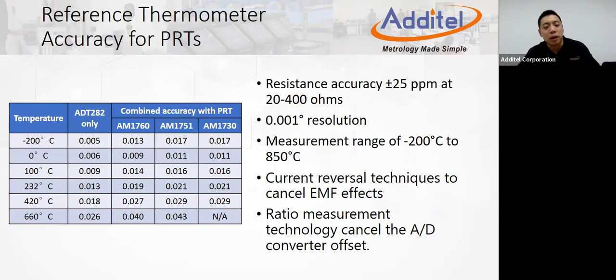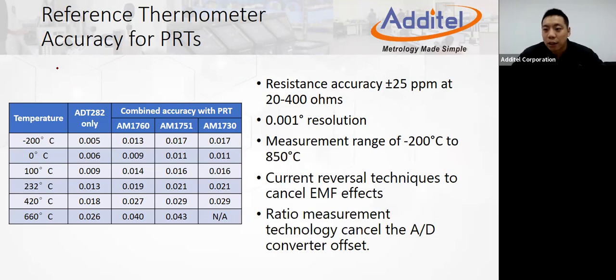For a reference thermometer readout, the most important thing is accuracy. We can easily find this in the table on the datasheet. Since this is a readout, normally we should consider 2 accuracies: the first is the readout itself, meaning the electronic measurement accuracy; the other is the combined accuracy with the PRT, meaning the readout accuracy plus the PRT accuracy together.